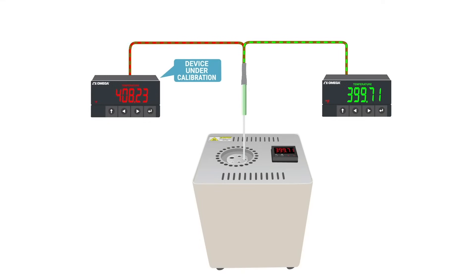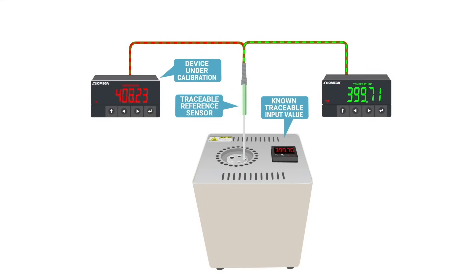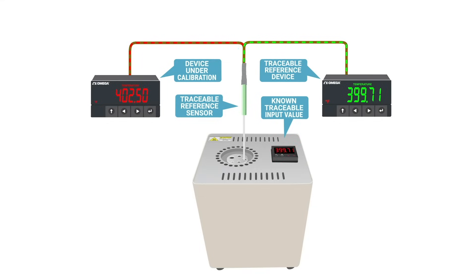The device under calibration is given a series of known input values across its entire measurement range. The output readings are compared to those of the calibration reference with the same input values applied. If a discrepancy is detected, adjustments are made to the device under calibration, bringing it back into its accepted accuracy range.